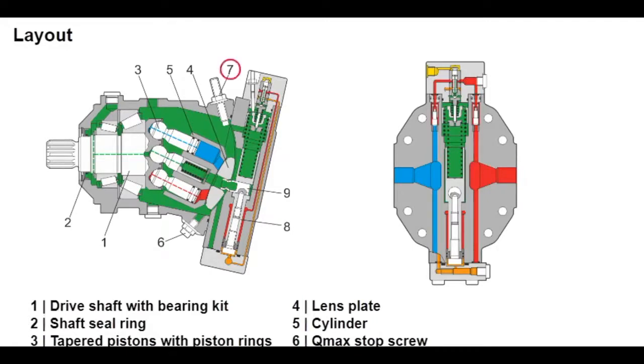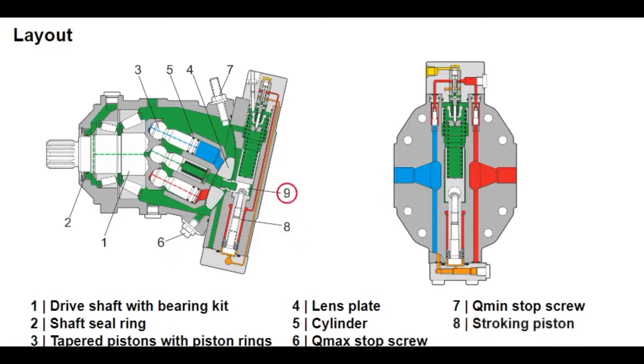The swivel angle is changed hydraulically using the stroking piston (8) and positioning trunnion (9). Here the cylinder, including piston and lens plate, is swiveled. The lens plate is smoothly mounted in a slipway. The swivel angle of the bent axis rotary group can be infinitely varied by using HD, EP, HA, and DA control.